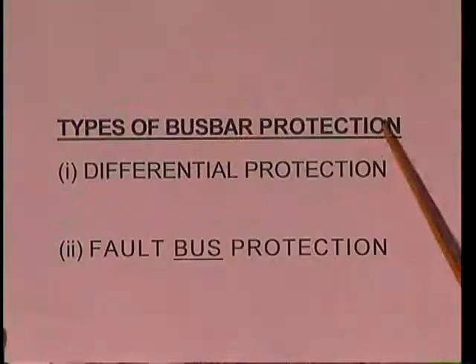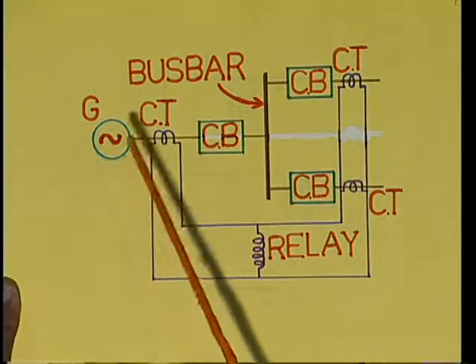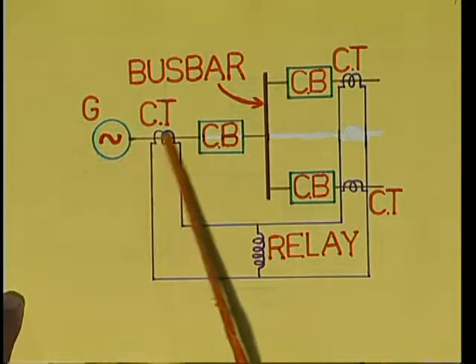Now coming to bus bar protection. Bus bars in generating stations or substations form an important link between incoming and outgoing circuits. Any fault on the bus bars causes considerable damage and disruption of supply. To ensure continuous supply, protection systems are also provided for bus bars. There are two types of bus bar protection: (1) differential protection, and (2) fault bus protection. In differential protection, a generator feeds the bus bar through a CT and circuit breaker. The bus bar supplies two outgoing lines, each through a circuit breaker and CT. All CTs are connected in parallel, and across this combination a relay (operating coil) is connected.